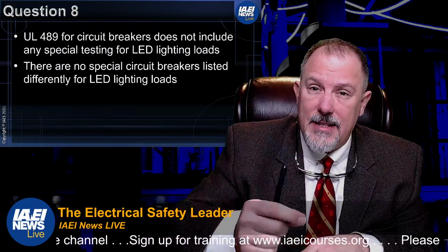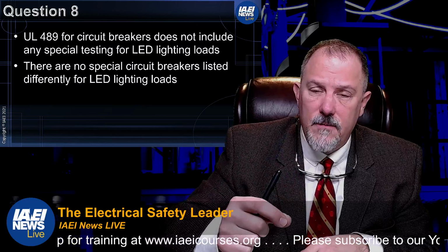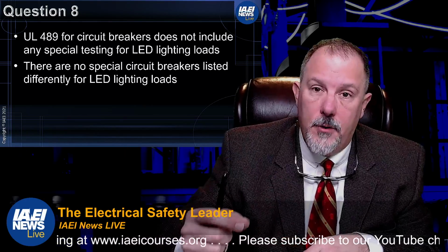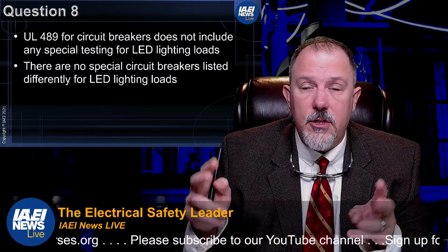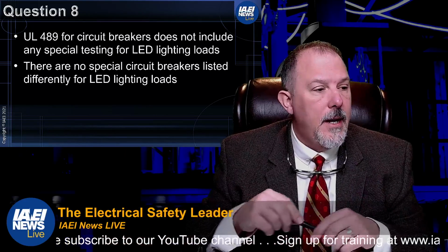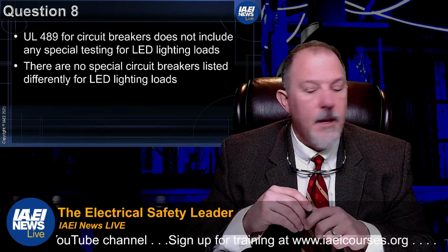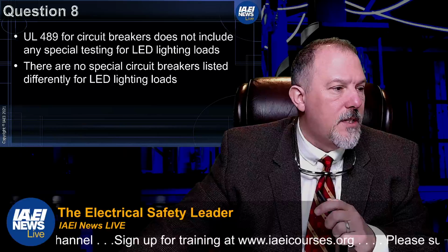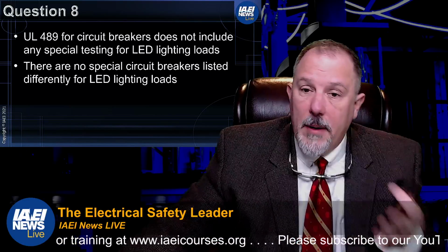That's the data point you're looking for on these circuits, for these types of loads, and then consider how many you have. And as a worst case, consider they're all turning on at the same time. That will give you some ideas. So that would be my suggestion.